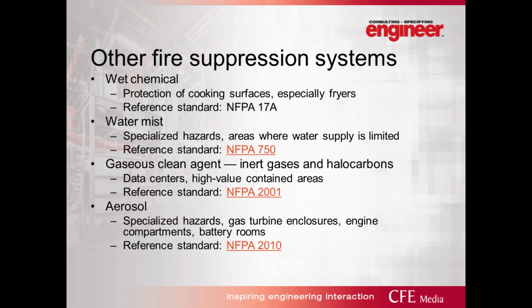Gaseous clean agent systems, which could take the form of inert gases or halocarbons, are used for data centers, high value areas. These have specific requirements because they are based off of maintaining a concentration of the agent in the room for a certain amount of time to stop the combustion process. So they must be in contained areas. They must be in enclosed spaces. You can't use a gaseous clean agent in an open space or an open area.